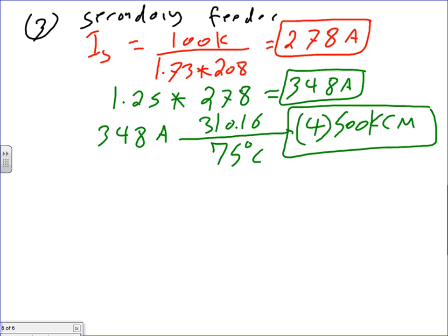Now here's where you can monkey around, guys. If you know your load, you can start derating the neutral. But in this case, we're carrying full neutral. See where this becomes happy? Because how do you derate the neutral in a transformer? I'll tell you how. You need to know what load the transformer is feeding. That's why I start with the load. I always start with the load.